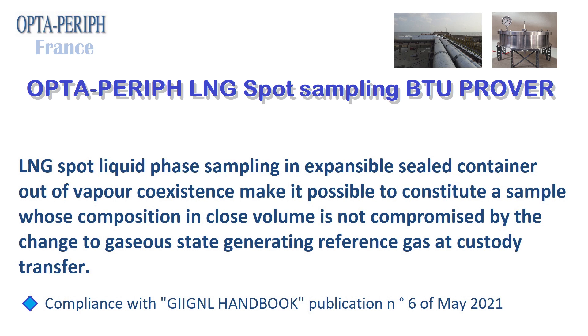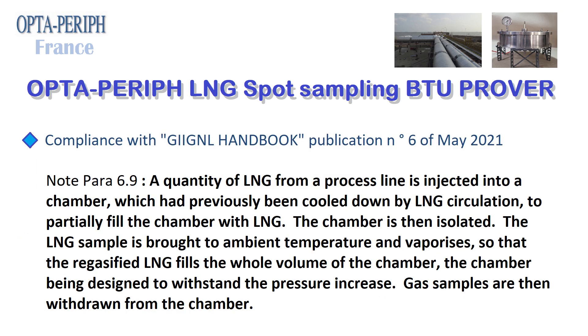LNG Spot Liquid Phase Sampling: Expansible Sealed Container, Out of Vapor Coexistence. This makes it possible to constitute a sample whose composition in close volume is not compromised by the change to gaseous state, generating reference gas at custody transfer. Compliance with GIIGNL Handbook Publication No. 6 of May 2021, Note para 6.9: a quantity of LNG from a process line is injected into a chamber which had previously been cooled down by LNG circulation to partially fill the chamber with LNG. The chamber is then isolated.